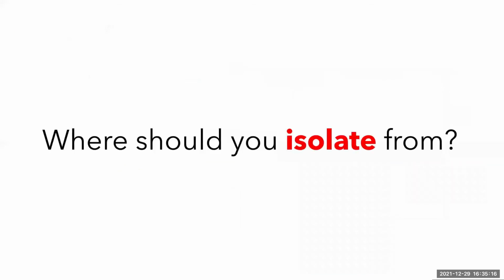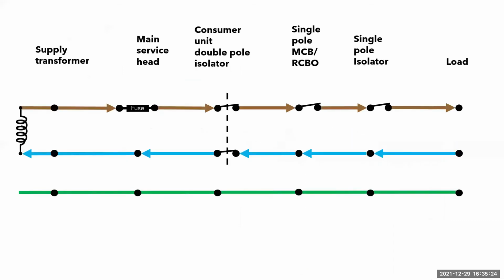A big problem for a lot of apprentices is where they should actually isolate from. When performing safe isolation, you need to consider what accessory you are isolating and ensure that you are isolating upstream so that you remove any sources of energy as you gain access to live parts and basic insulation within an enclosure.